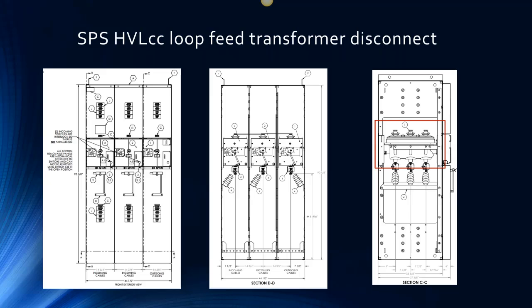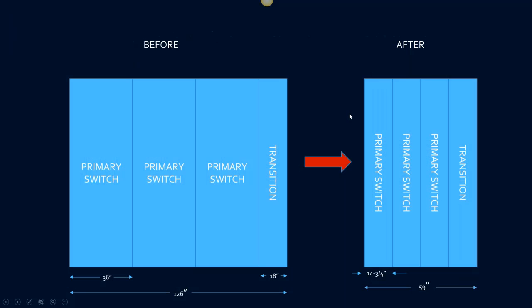But that is not a requirement in IEC land, but I'll tell you, it is sure a convenience and a very effective safety solution as well. So it meets all the requirements of NFPA 70E Article 120.5 for visible confirmation of blade disconnect and visible confirmation of grounding. So thank you, Michael. Great, Mike, thank you. So in addition to all those benefits, let's look and see how we did.